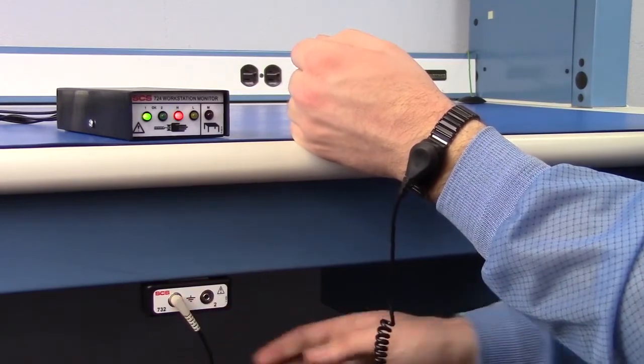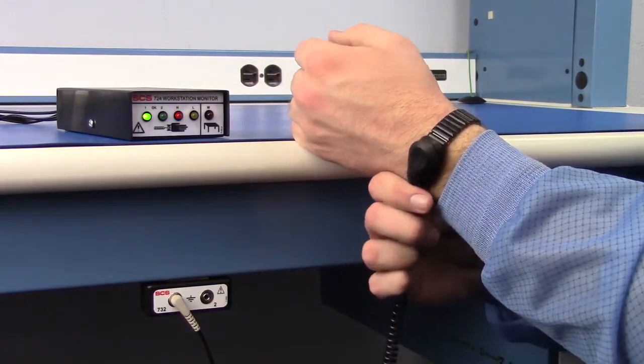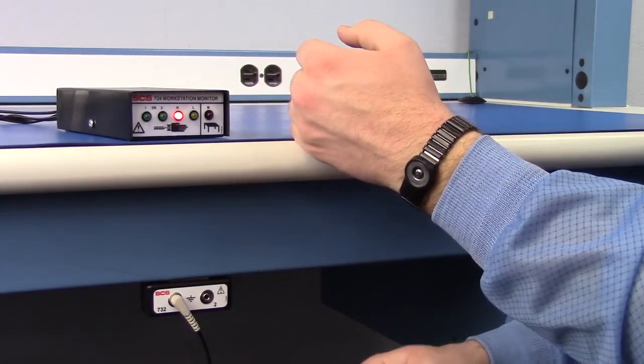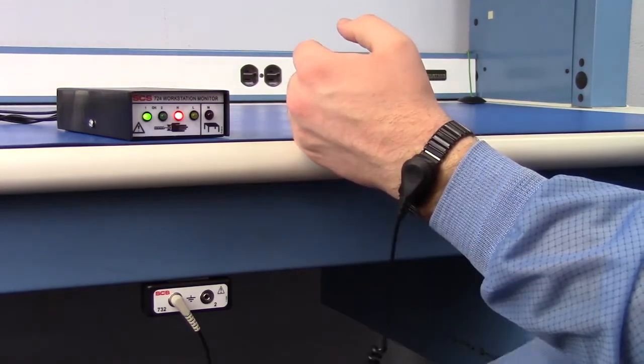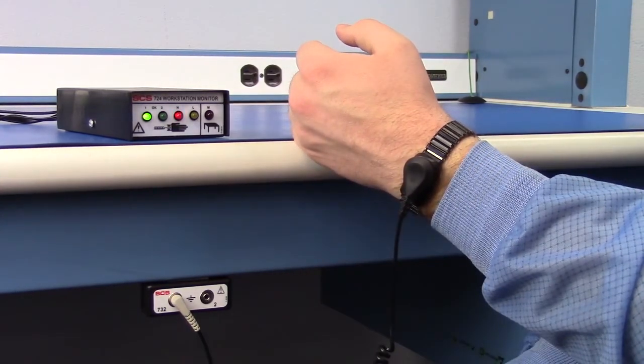The SCS724 Workstation Monitor is now ready to monitor an operator. Fit a dual-wire wrist strap snugly to the wrist and plug its wrist cord into operator remote jack number one. The operator is now grounded and monitored for connectivity and resistance range. Use operator remote jack number two when a second operator is to be monitored at the workstation.